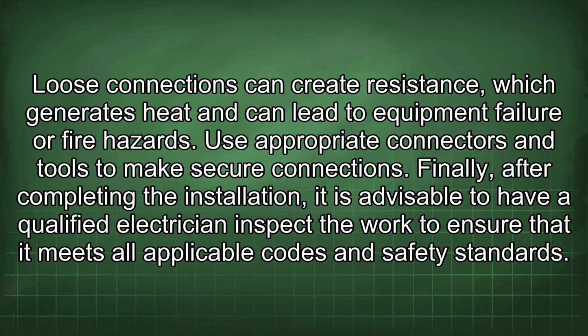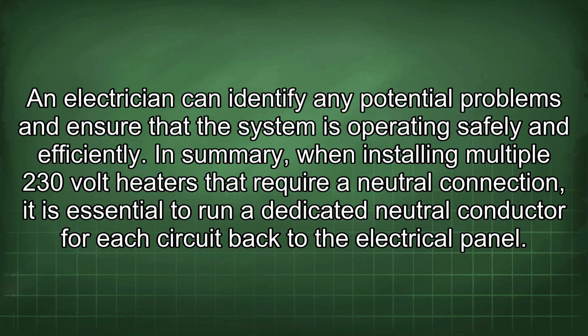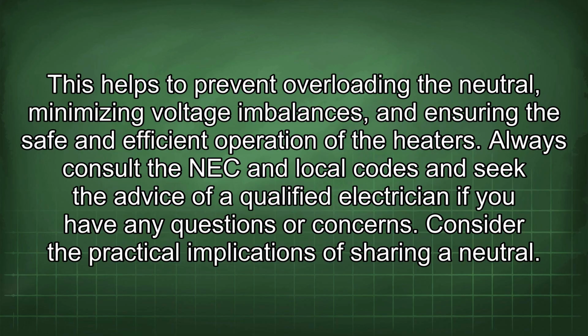Finally, after completing the installation, it is advisable to have a qualified electrician inspect the work to ensure that it meets all applicable codes and safety standards. An electrician can identify any potential problems and ensure that the system is operating safely and efficiently. In summary, when installing multiple 230-volt heaters that require a neutral connection, it is essential to run a dedicated neutral conductor for each circuit back to the electrical panel. This helps to prevent overloading the neutral, minimizing voltage imbalances, and ensuring the safe and efficient operation of the heaters. Always consult the NEC and local codes and seek the advice of a qualified electrician if you have any questions or concerns.